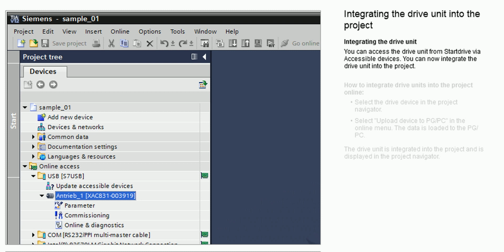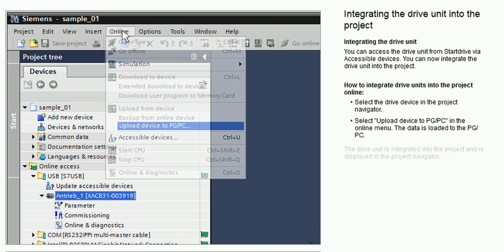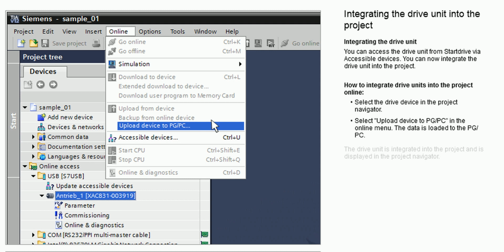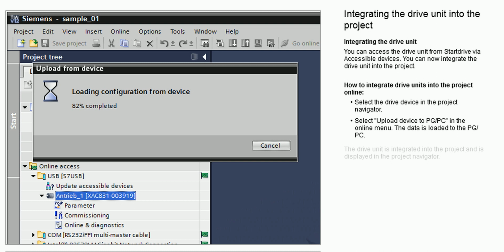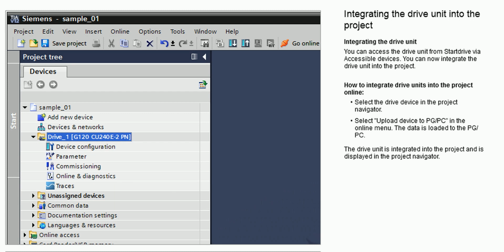Integrating the drive unit into the project. You can access the drive unit from Startdrive via accessible devices. You can now integrate the drive unit into the project. How to integrate drive units into the project online. Select the drive device in the Project Navigator. Select Upload Device to PG-PC in the Online menu. The data is loaded to the PG-PC. The drive unit is integrated into the project and is displayed in the Project Navigator.